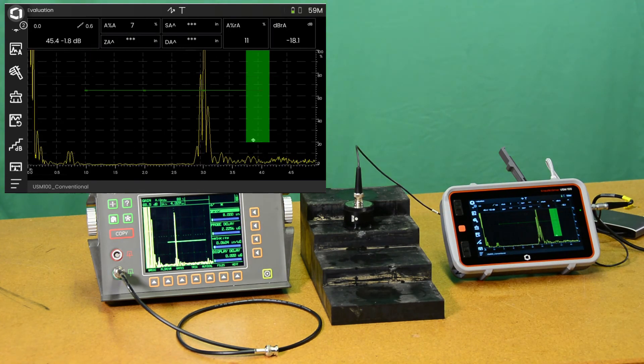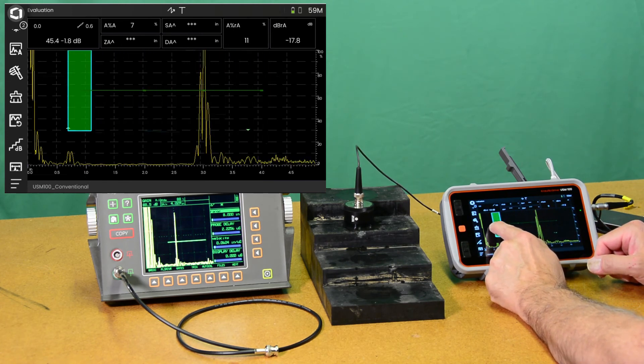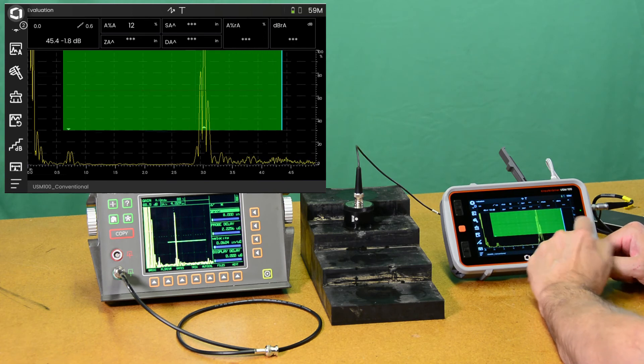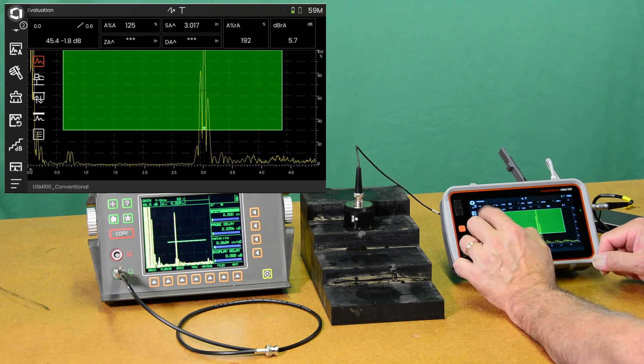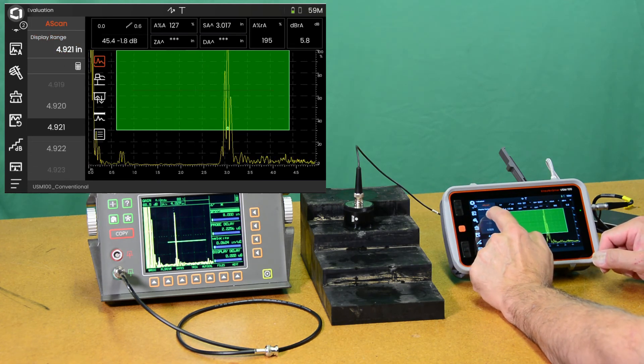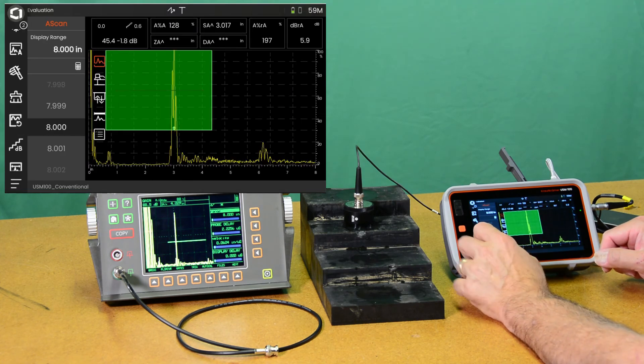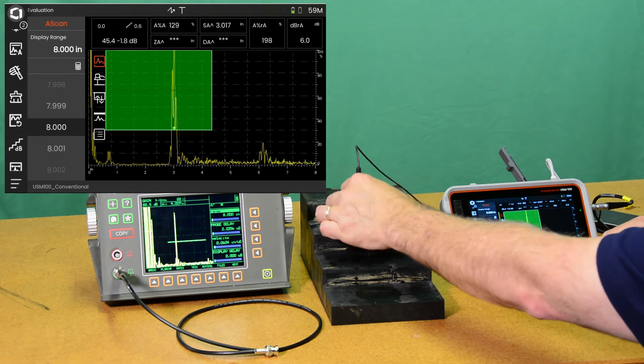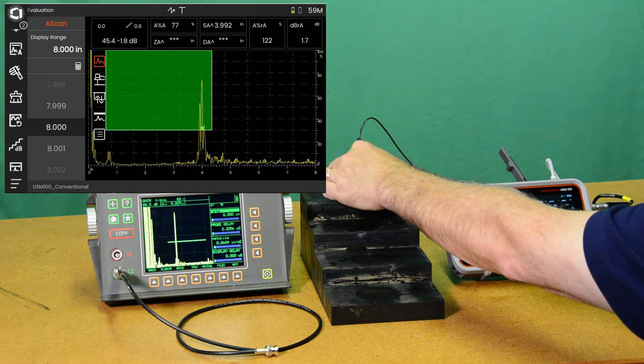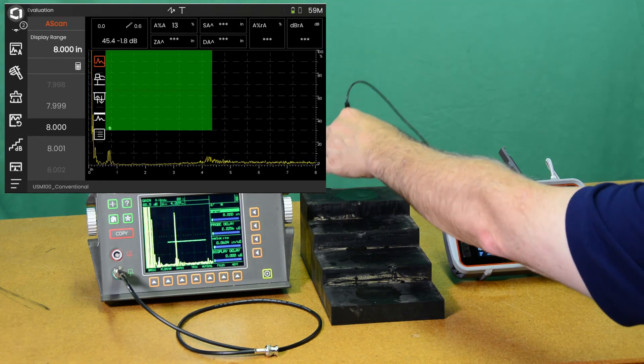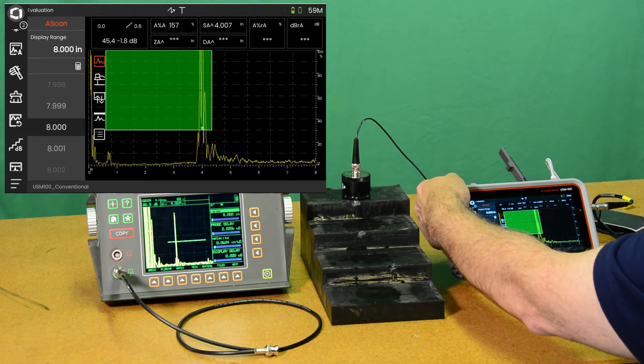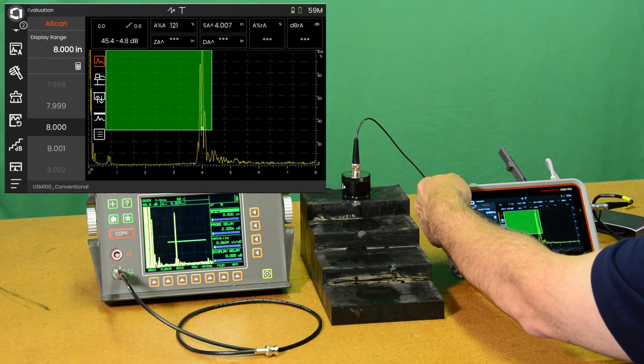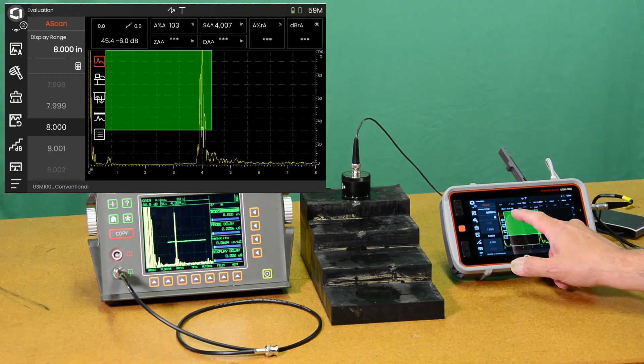So there we go. And we can hide that menu. So now we have a setup that allows us to take, if I widen my gate here by touching and dragging on the screen. Maybe I want to go to a wider A-scan. I think we had eight inches on our USN 60. So let's set that up the same. So there's eight inches. We're at half screen. The four inch step. Gain out.